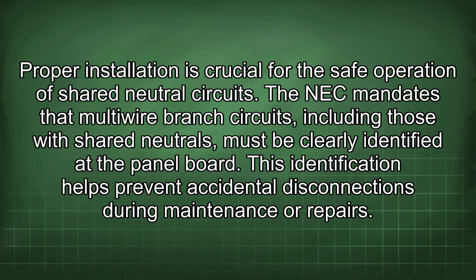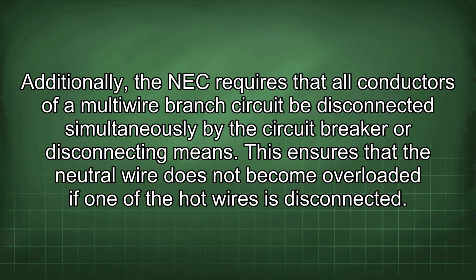This identification helps prevent accidental disconnections during maintenance or repairs. Additionally, the NEC requires that all conductors of a multi-wire branch circuit be disconnected simultaneously by the circuit breaker or disconnecting means. This ensures that the neutral wire does not become overloaded if one of the hot wires is disconnected.